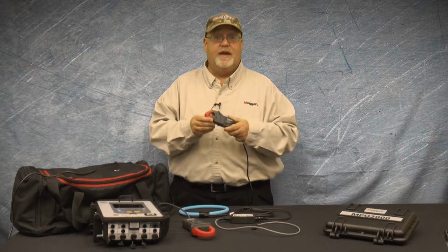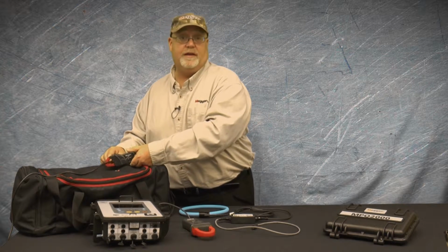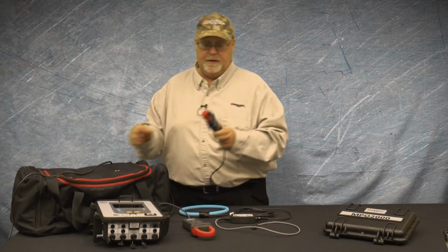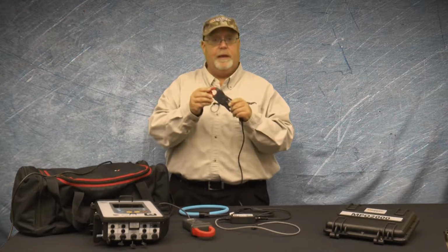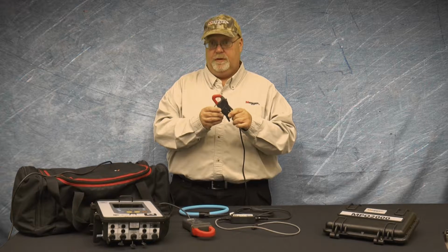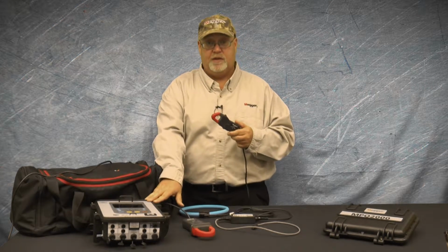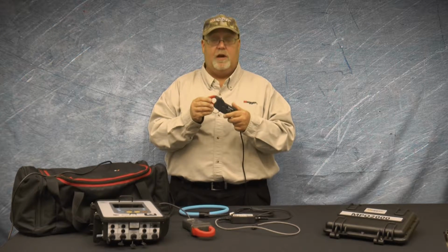As the name would suggest, the split core CT splits. This allows it to go around the wire that has to be tested. Now, the split core CT can have two different types of outputs. It can either have a current output or a voltage output. The split core CTs used with the Megger line of power quality instrumentation has a voltage output from 0 to 1 volt.